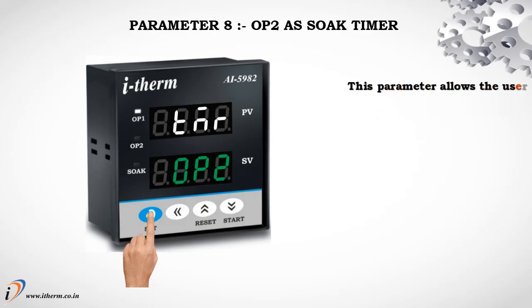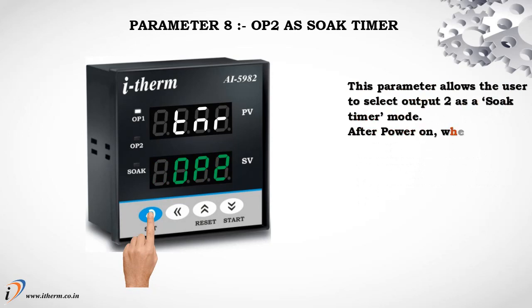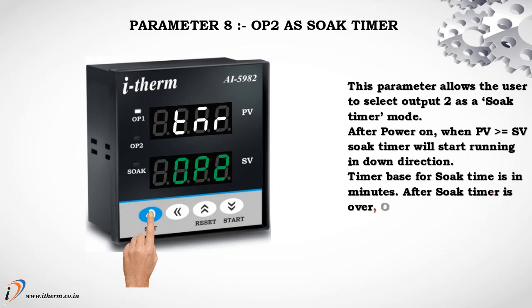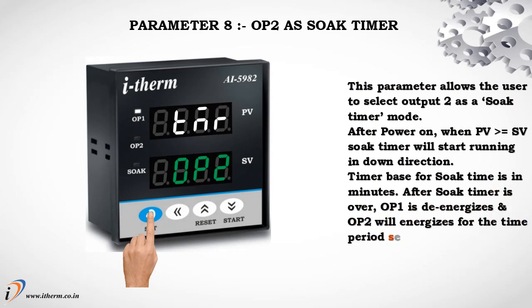Parameter 8: Output 2 as Soak Timer. This parameter allows the user to select output 2 as Soak Timer mode. After power on, when process value is greater than or equal to the set value, the Soak Timer will start running in the down direction. Timer base for Soak Timer is in minutes. After the Soak Timer is over, output 1 de-energizes and output 2 energizes for the time period set via Soak Timer delay.